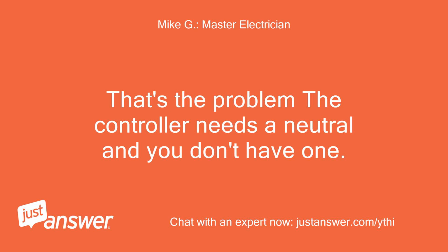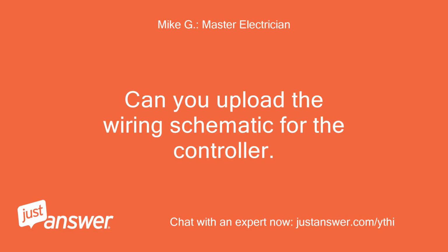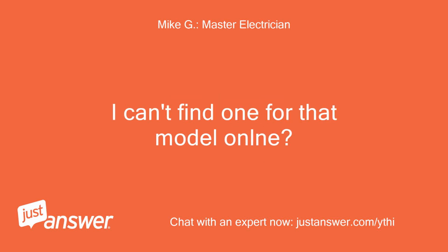That's the problem. The controller needs a neutral and you don't have one. According to instructions, it said do not connect neutral supply line to wall switch or damage could occur. Can you upload the wiring schematic for the controller? I can't find one for that model online.